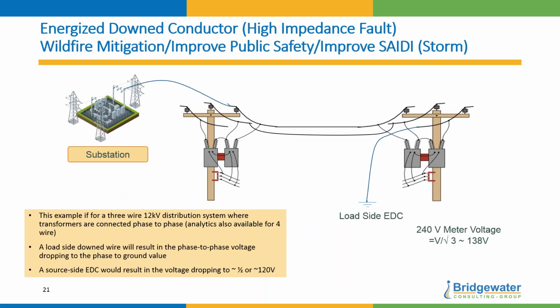The first one, and I've been on IEEE committees and been involved with this many times, is the wire down, the energized down conductor, high impedance fault. Well, on the West Coast here, we did a lot of work and found that yes, we can identify wire downs with pretty good accuracy in near real time. We have a 3-wire system out here, but this can also work on a 4-wire, but a lot of the work that I did is on 3-wire systems.